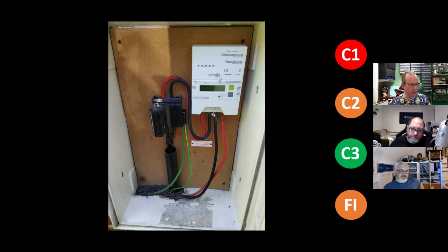And the problem here is you can look at what's in the cavity now, because of course originally the cavity was empty when it was constructed sort of 30 years ago, and subsequently somebody has come along and injected those insulation beads into the wall cavity. Yeah, those new innovations to lower our energy losses and potentially set fire to every building. Yeah, and how many pictures do we have on our Instagram page alone of boards that are filled with those beads? It's mind-blowing.